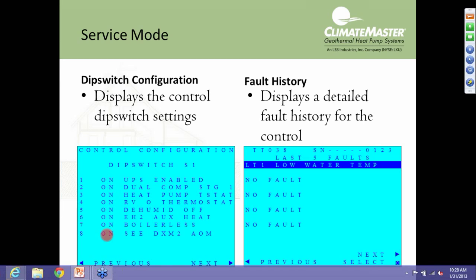All these dip switches under most residential applications... Number 7 is that boiler cooling tower. Again, we typically are not doing that in a residential application, so that should always be in the on position.